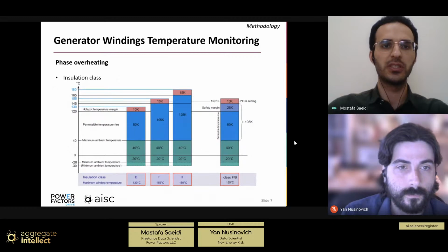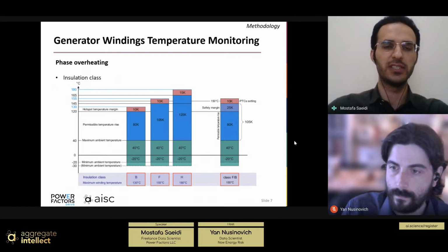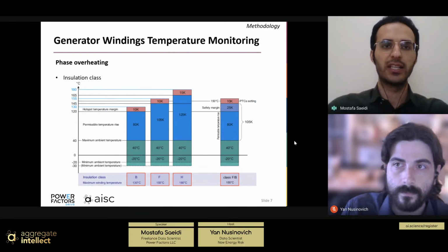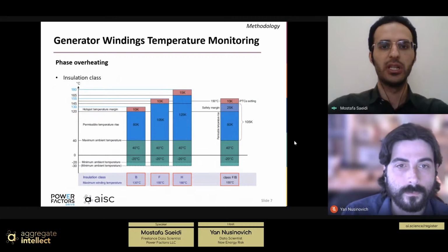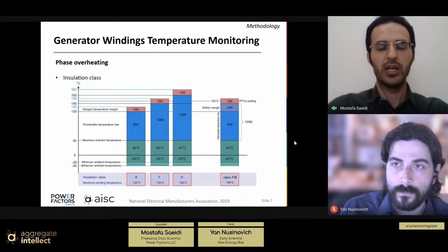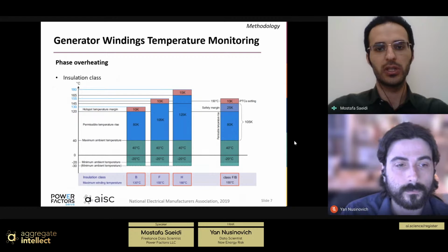In our study, we focused on the windings of the generators and we try to focus on the temperature monitoring for them. The first step was to define overheating and the normal temperature. For that, we refer to the standards, which suggested that there is a term for that, insulation class. Each generator has an insulation class for the cables or the windings inside generators. This insulation class has a maximum allowable temperature, which is suggested by the standards. In our case study, the generator we were focusing on had insulation class F, in other words, the maximum allowable temperature for operation of these generators was 155 degrees centigrade.